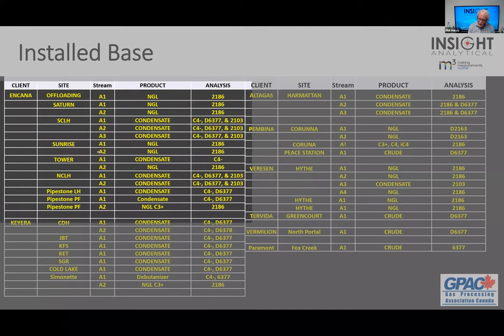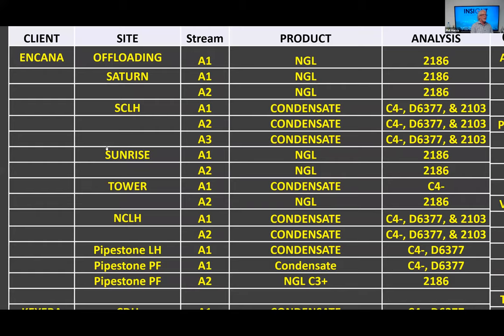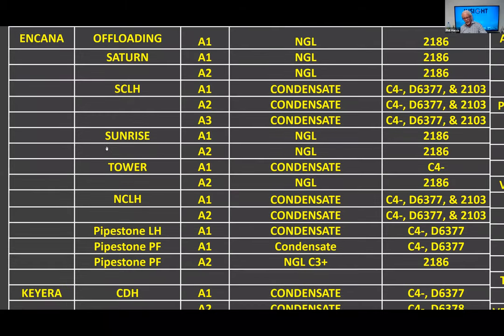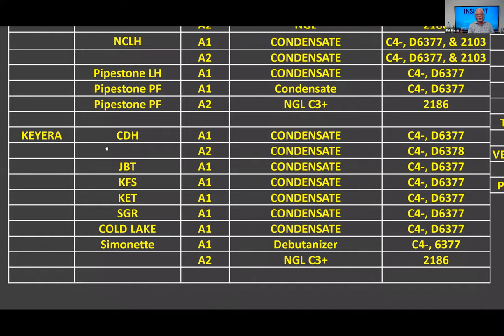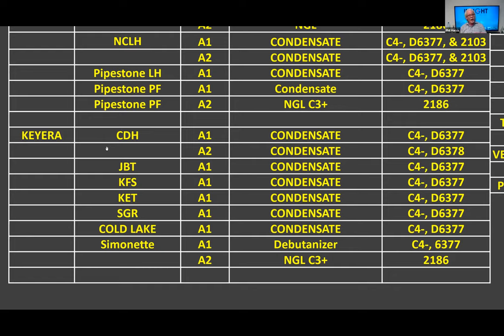We put the first one in Canada in 2016 — that was the Tower gas plant. Every gas plant that Canada put in since then has this technology on the liquid side, on every C3 stream and every C5 plus stream. We ran in parallel with an existing GC and existing online vapor pressure for a year at Josephburg Terminal, showing that we can get the same results with far less maintenance. People talk about putting $50,000 worth of parts into their GCs a year on streams like this, plus maintenance time. We ran on a crude blending skid and nobody touched it for nine months.